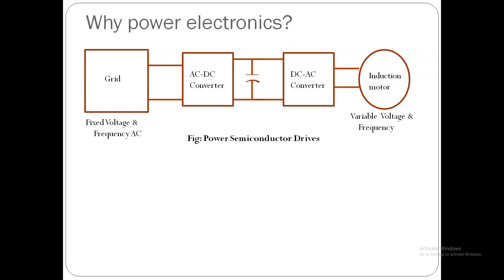A two-stage Power Electronics converter is considered as a solution: an AC to DC converter to convert AC supply from the grid into DC at the DC link, and a DC to AC converter to convert DC at the link into the required AC. This way, one can control the output voltage of the DC to AC converter and thus control the speed of the induction motor.